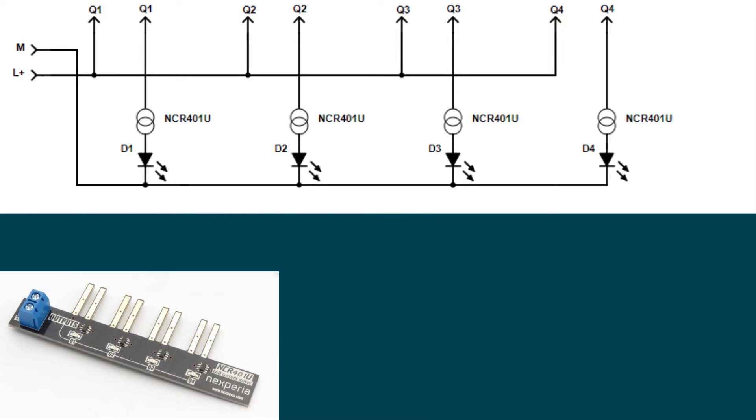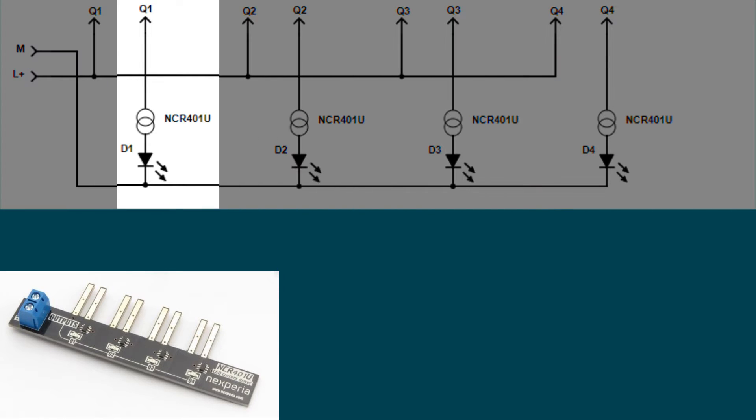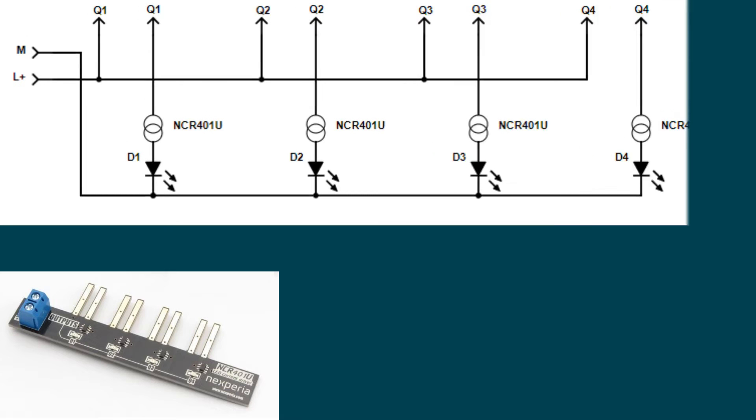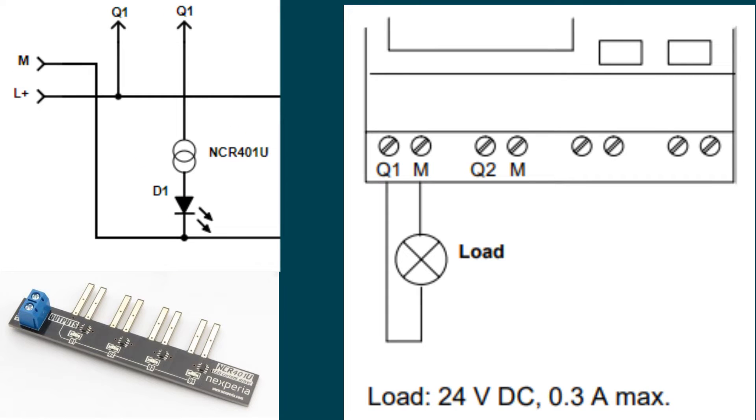The output module has 4 identical circuits consisting of a constant current LED driver and LED driven by the right side terminal of each relay output. L plus is fed in on the left terminal. The LOGO 24V DC transistor outputs have all the right side terminals connected internally to M, so they won't drive the output simulator correctly.